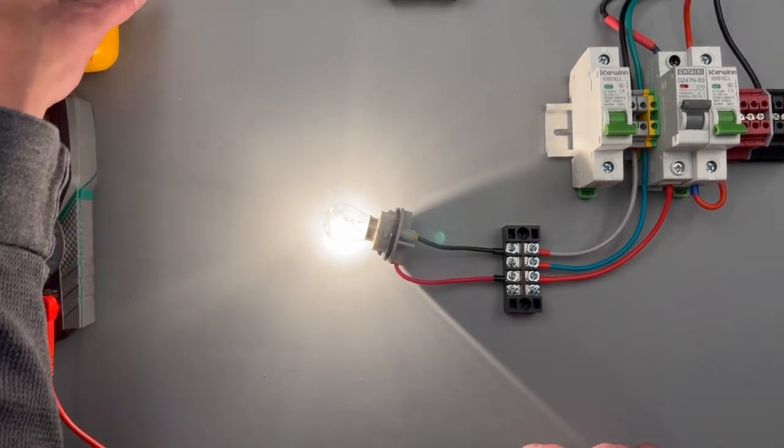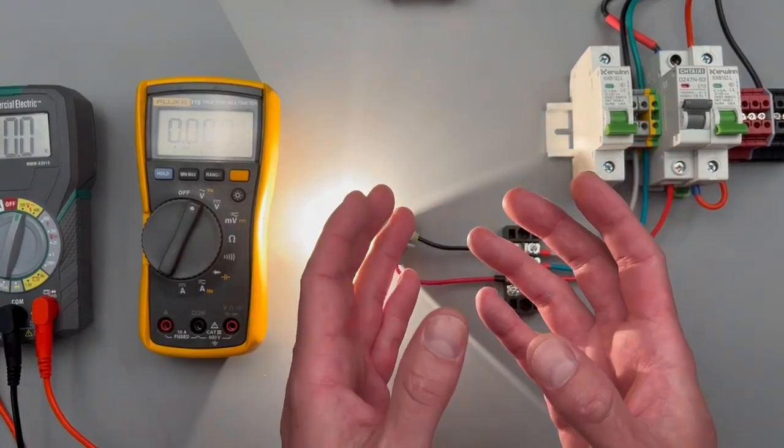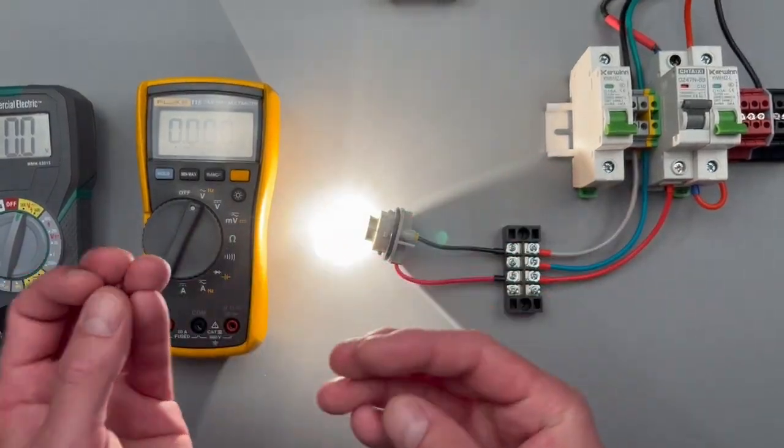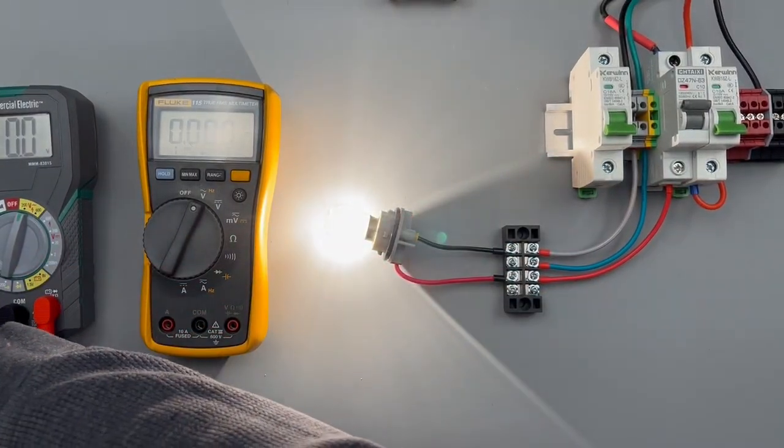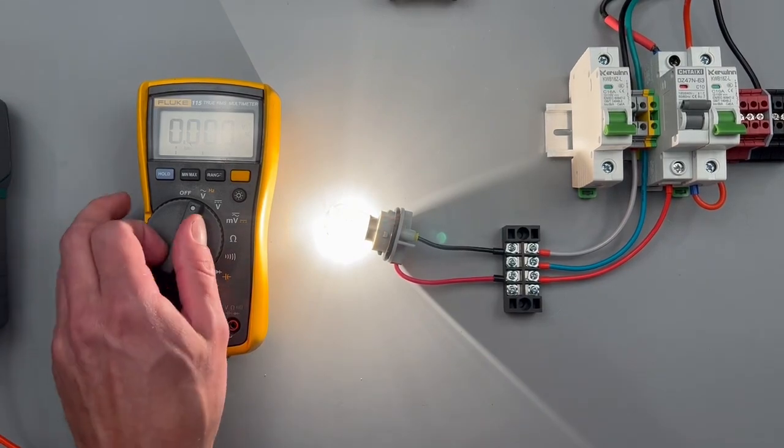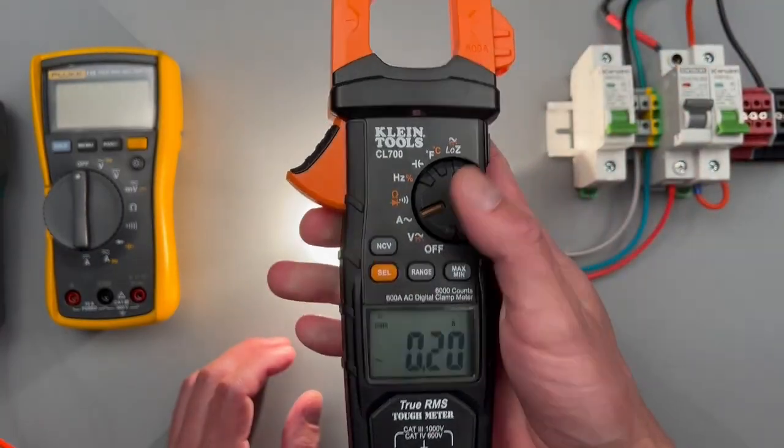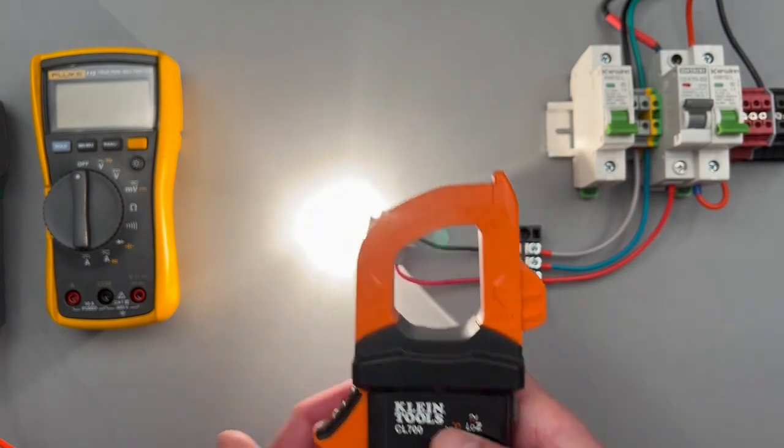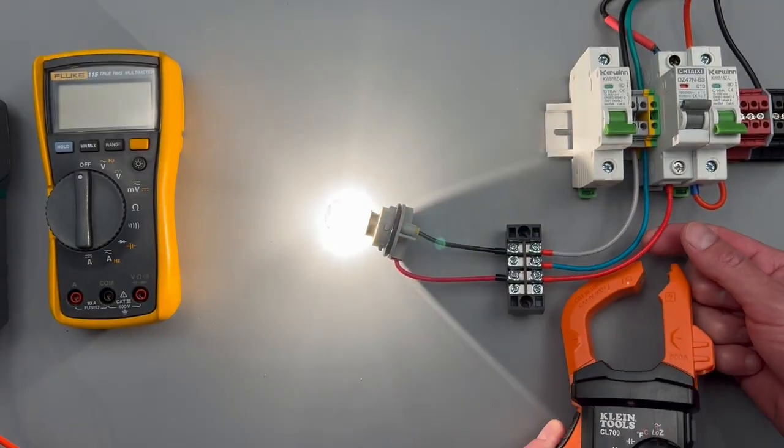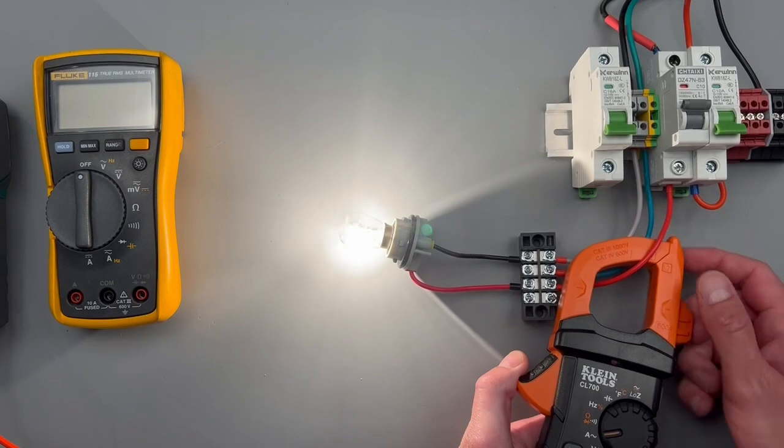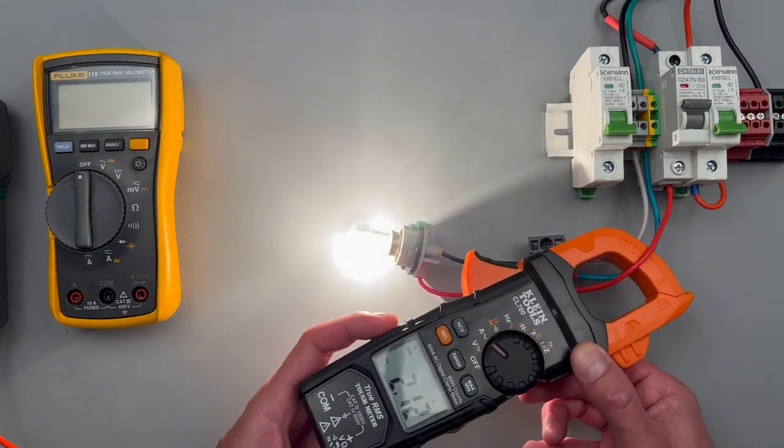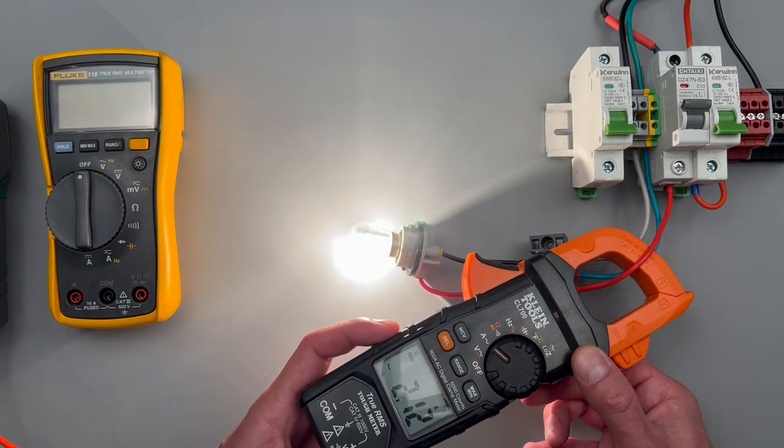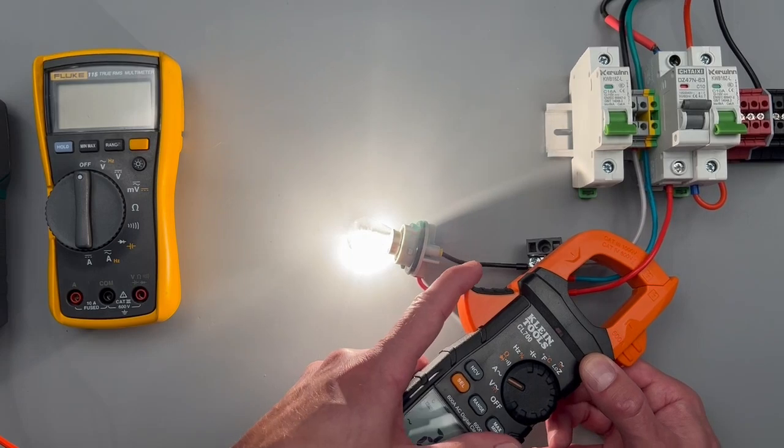For measuring current we can either use an amp clamp or we can measure in series. On this meter it's only rated for AC amperage—that's what the clamp's rated for. You're going to want to put your amp clamp around either the hot or the neutral, but not both. It's showing me it's drawing two amps of current. Now I can do that around the neutral wire and still get the same reading.